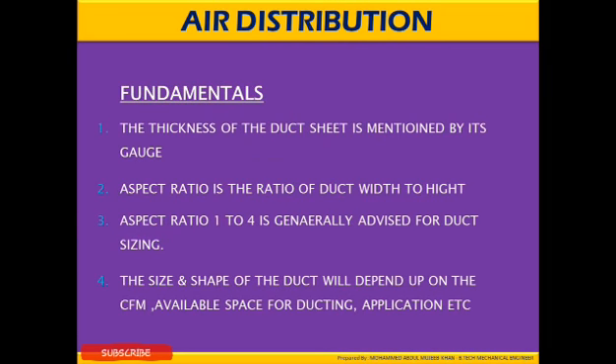The thickness of the duct sheet is mentioned by its gauges. Aspect ratio is the ratio of the duct width to height. Aspect ratio 1 to 4 is generally advised for duct sizing. The sizes and shapes of the ducts will depend upon the CFM, available space for ducting, application, etc.